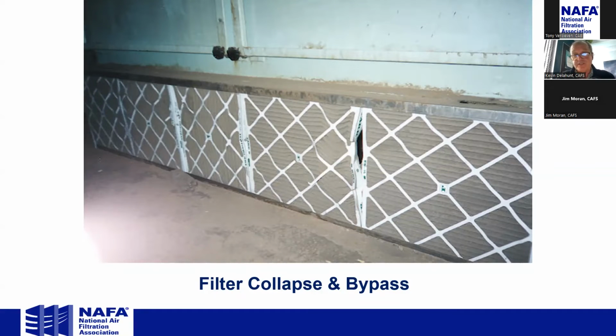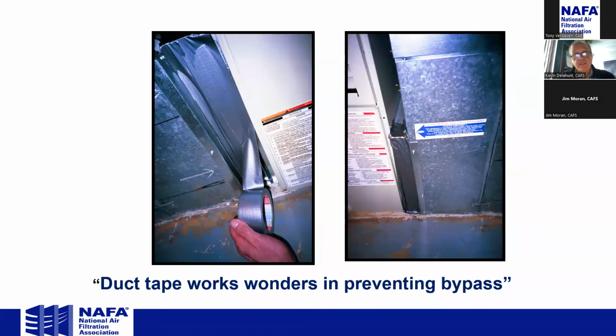So very evident, but it also brings to attention the need to look at filters on a regular basis, not just at time of installation and removal, but throughout the life cycle of the product, so that you can see these things develop and rectify them as they happen. Okay. The fixes are a lot of times very inexpensive, and even in this furnace application, just duct taping the filter, and sealing where the door should have been, and whatever that costs, maybe 12 cents worth of duct tape to hold the filter in place, make sure all the air is going through the filter, and upon replacement, again, just putting some new duct tape in there so the filter sits in place and does what it's supposed to do.